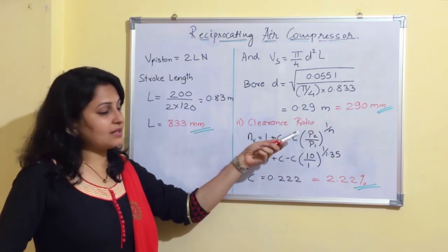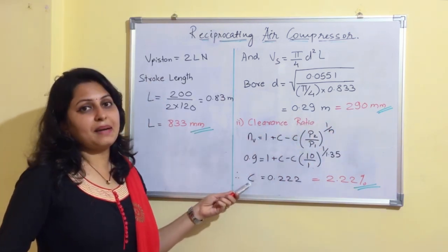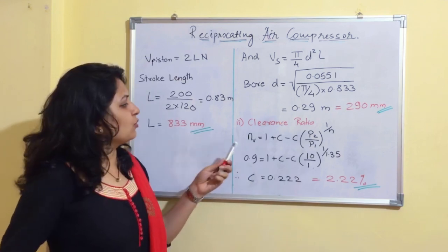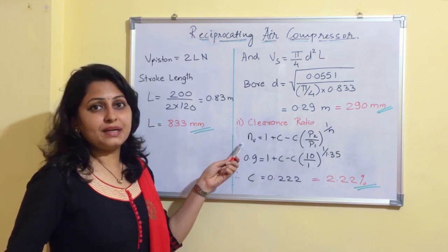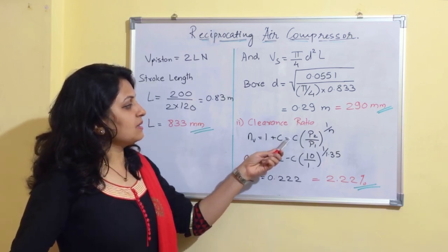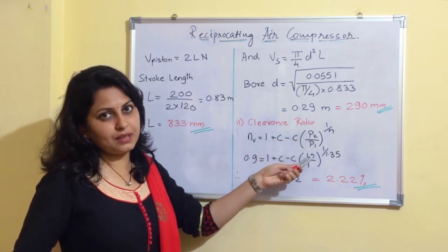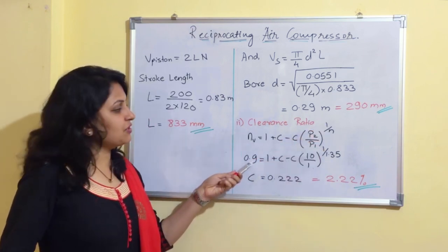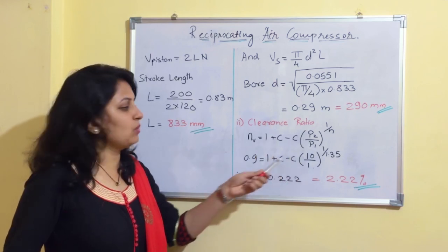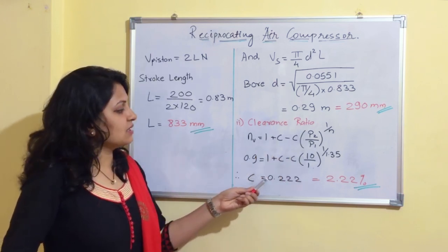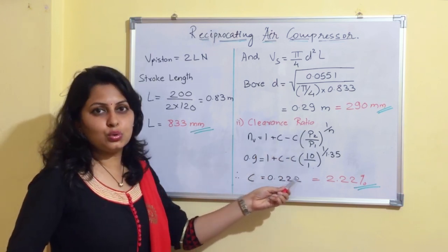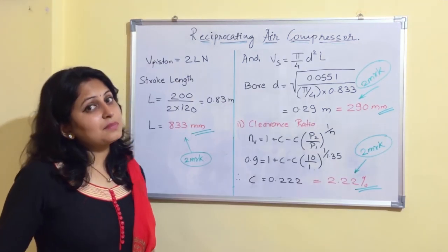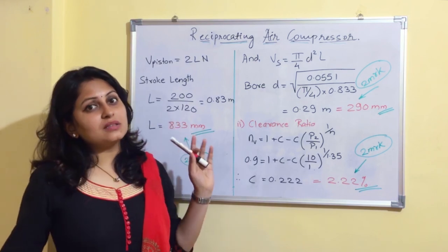The next point is to find the clearance ratio C = Vc/Vs. Using the volumetric efficiency formula: η_vol = 1 + C − C·(P2/P1)^(1/N), and substituting volumetric efficiency = 90% and pressure ratio P2/P1 = 10, we get C = 0.222. This is typically expressed as a percentage.